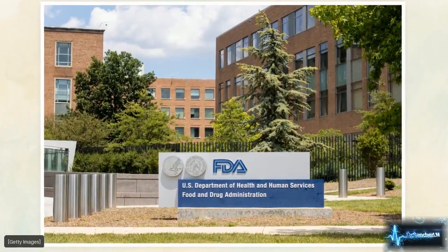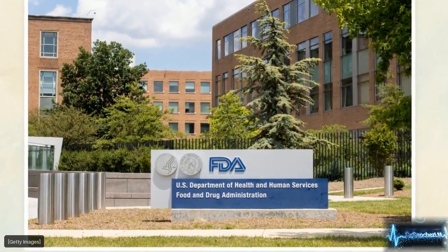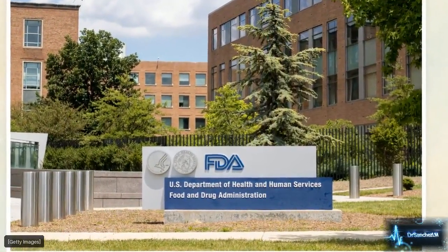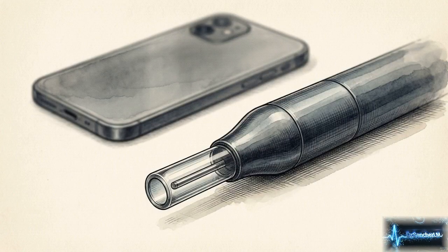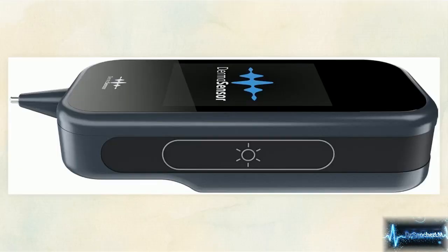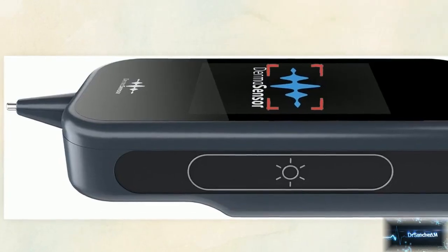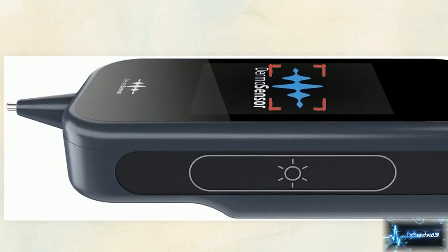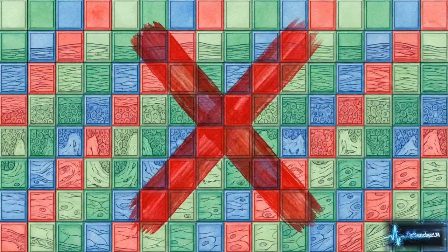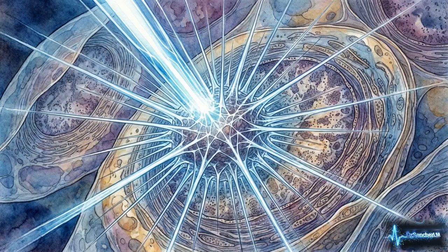To solve this problem, the U.S. Food and Drug Administration recently cleared a new category of medical device built specifically to bypass the flaws of smartphone cameras. This is DermaSensor, a new hardware class designed for primary care physicians. It completely abandons two-dimensional photography. Instead, it relies on elastic scattering spectroscopy, or ESS, an optical technique distinguishing normal from abnormal tissue by recording how photons scatter. To reliably detect malignant tissue, diagnostic tools must stop analyzing the superficial color of the skin and start measuring its physical, subcellular structure.